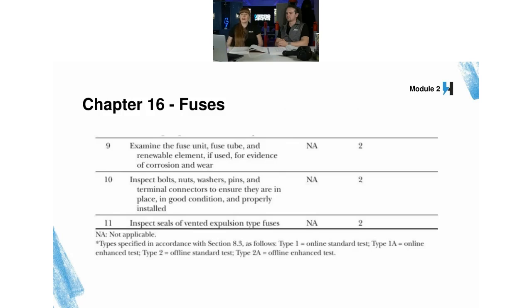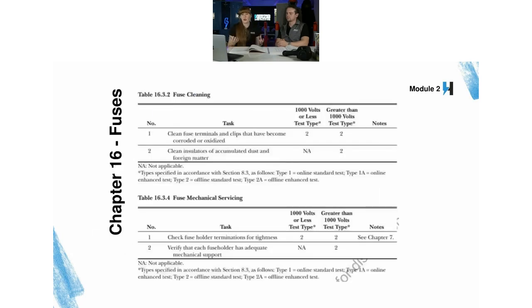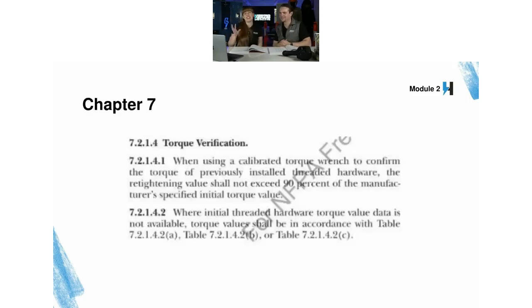Okay, and then the mechanical servicing, so just making sure that the fuse holder terminations are tight enough, for example, and then again, the other one doesn't apply to low voltage. Tight enough, meaning they're tight according to the manufacturer's instructions, or if no data is available, you should refer to Chapter 9. There are tables. Chapter 7, I'm sorry. Chapter 7, it's right here. I'm getting those mixed up already, aren't I? So torque verification, 7.2.1.4.1 and 2.